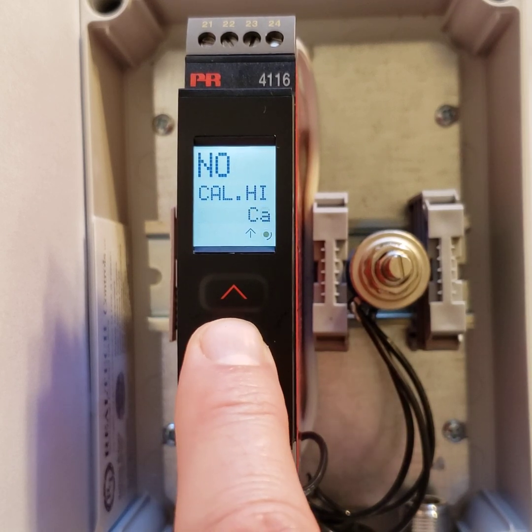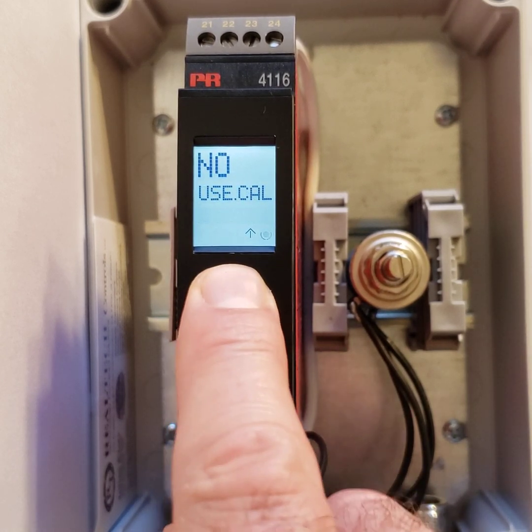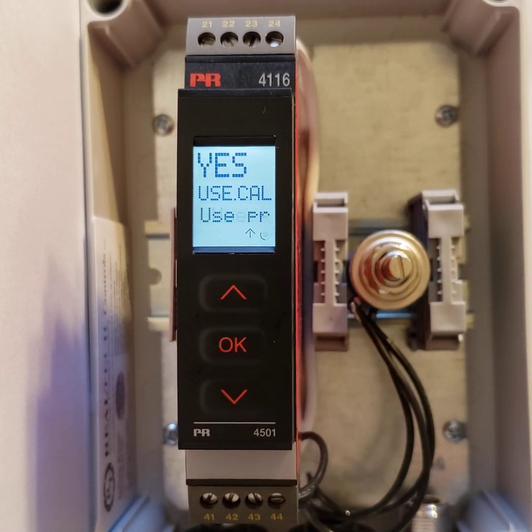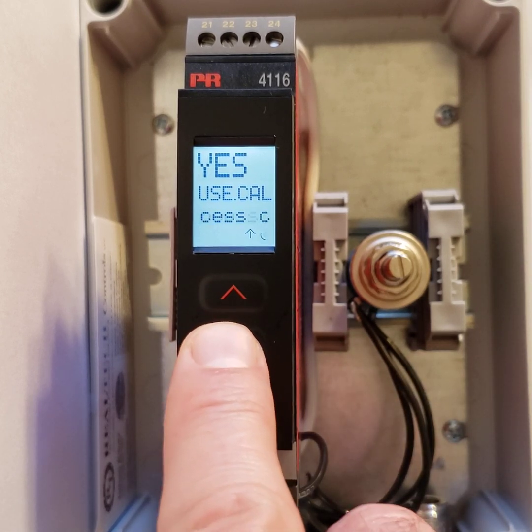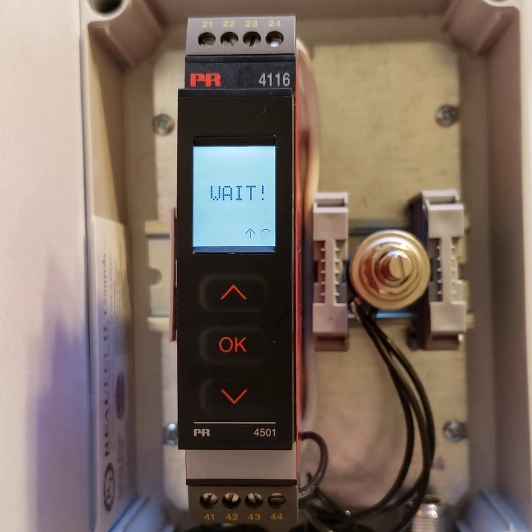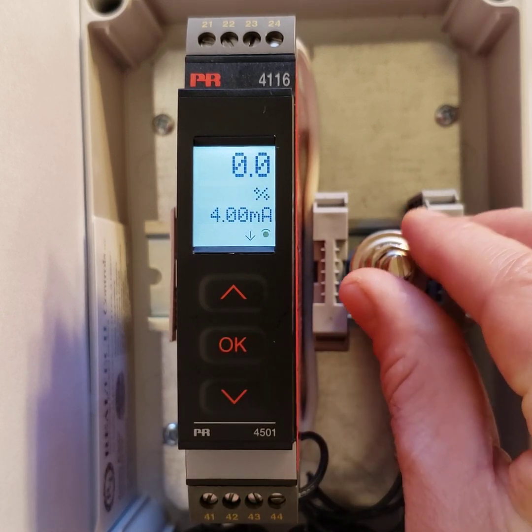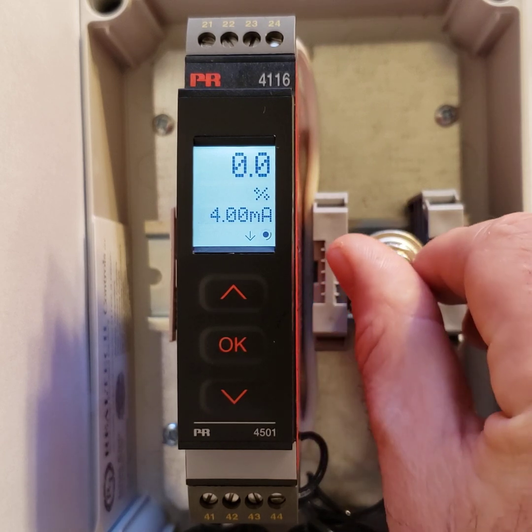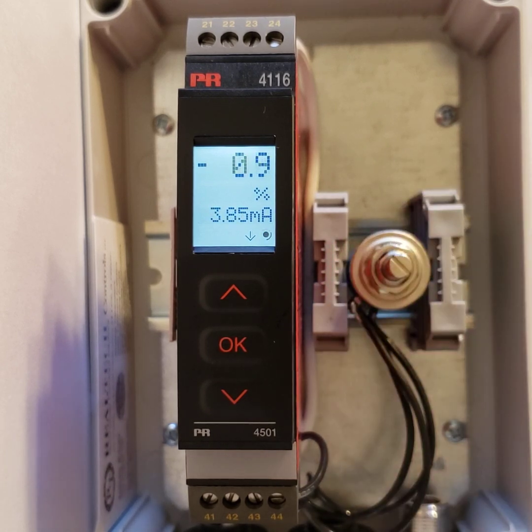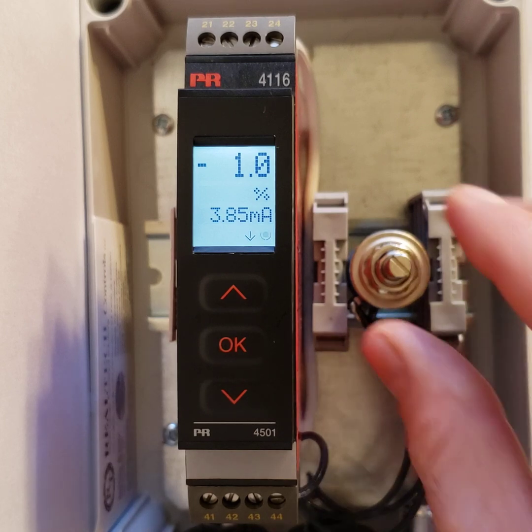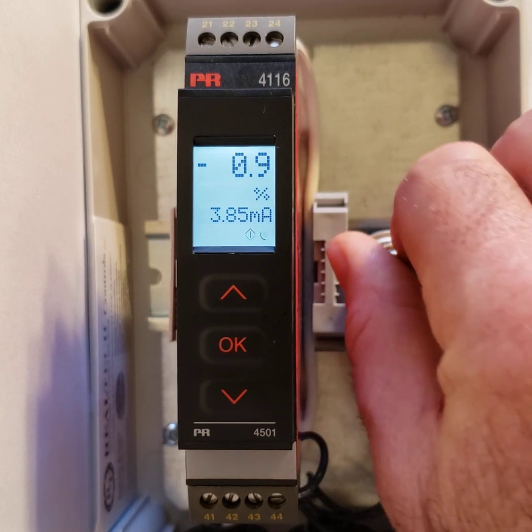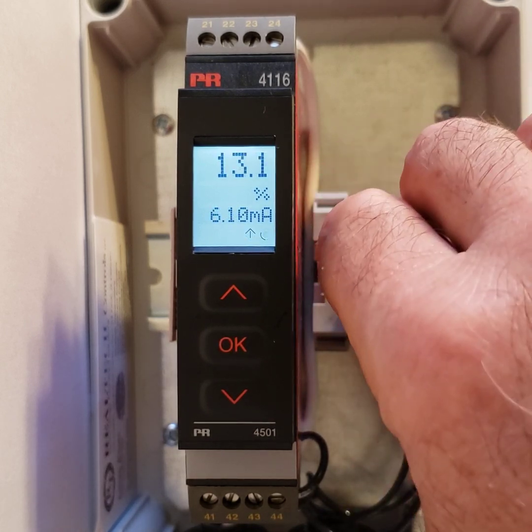Do you want to calibrate the high? Not yet. Use calibration. There's an option to use or cancel out the calibration you've done. If I choose yes, now you'll see that at 0% of my pot, it's actually showing me 4. And if I go all the way down, you'll see that there's my -1%. So it does let you go lower. So now I'm going to adjust the pot all the way up.